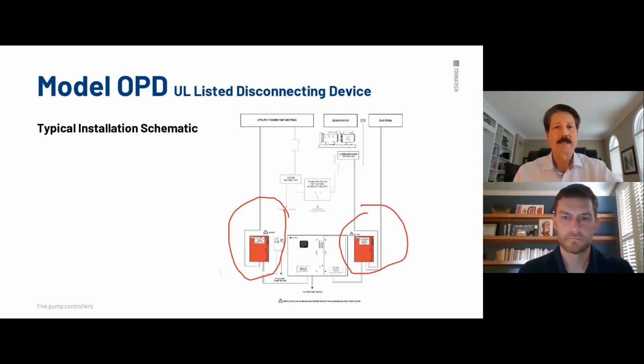That is the ideal application because number one is you don't have to worry about incoming power. You don't have to deal with coordinating a shutdown with the utility company. And I've dealt with many cities across the US dealing with power facilities, power companies, and they'll tell you up front, we don't have the resources to answer the demand to cut power off at a facility and then come back and turn it back on based on your time frame. It's probably very rare. It's going to be based on their time frame. So again, having an OPD like this eliminates the need to even worry about contacting and coordinating a shutdown time with the local municipality or the power company itself.